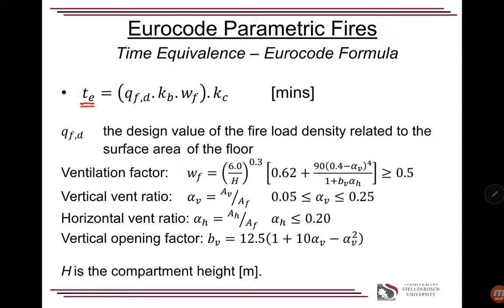And here's our equation. So we've got a time equivalent, so that's an equivalent standard fire rating, and that is based upon the design fuel load, which we have calculated previously. And then this is adjusted by certain factors to account for boundary conditions, ventilation, and then the type of construction used. And this is a value in minutes. So, as I said, q subscript fire, d, the design value of the fire load density related to the surface area of the floor, not the boundary, the floor.